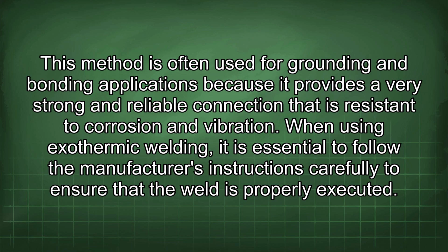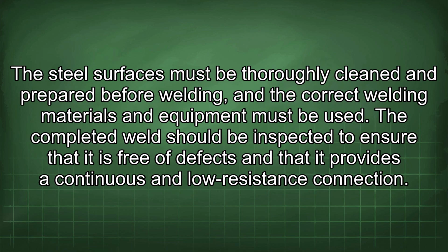When using exothermic welding, it is essential to follow the manufacturer's instructions carefully to ensure that the weld is properly executed. The steel surfaces must be thoroughly cleaned and prepared before welding, and the correct welding materials and equipment must be used. The completed weld should be inspected to ensure that it is free of defects and that it provides a continuous and low resistance connection.